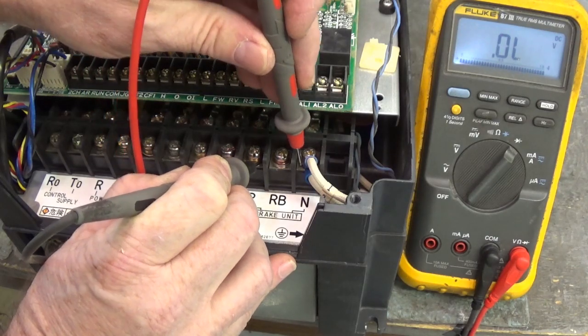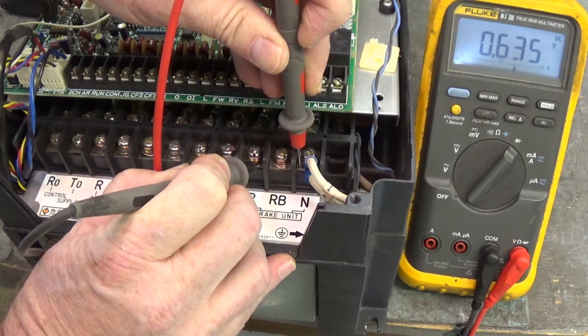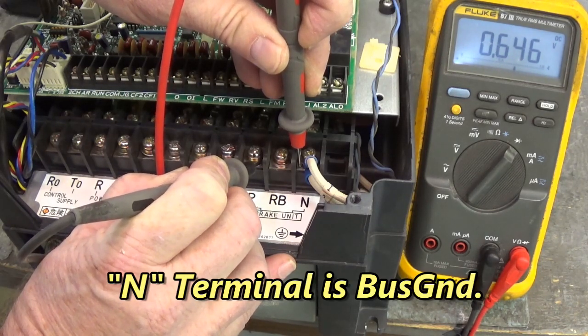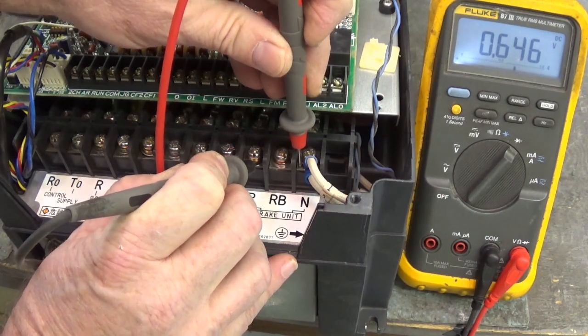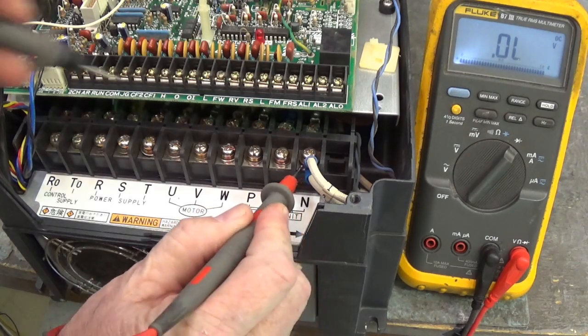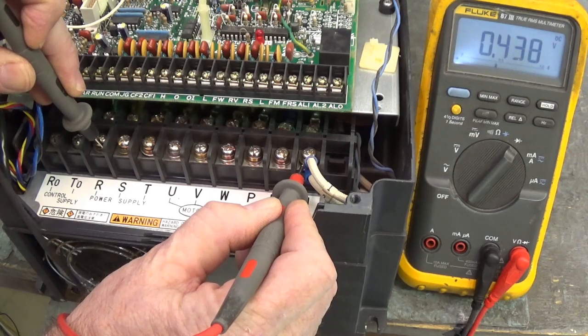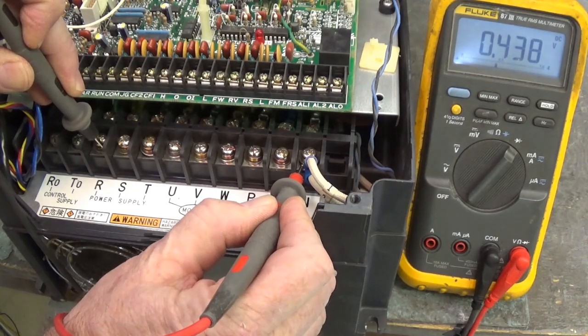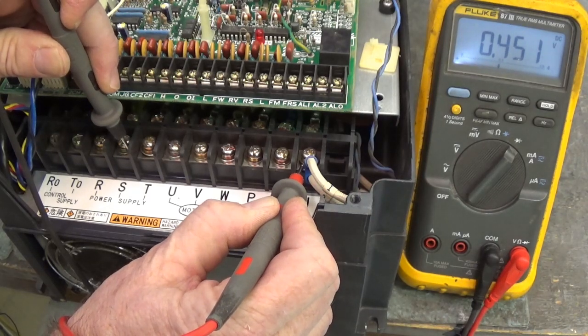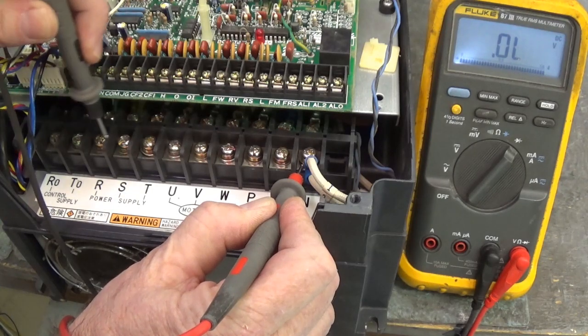We're charging up the bus cap. I've moved the red lead to N — that's bus ground — diode drop of 0.646. Now keep the red lead on N, black lead on R: 0.438. Here's S: 0.451. That's good so far — that's our three-phase bridge on R, S, and T.